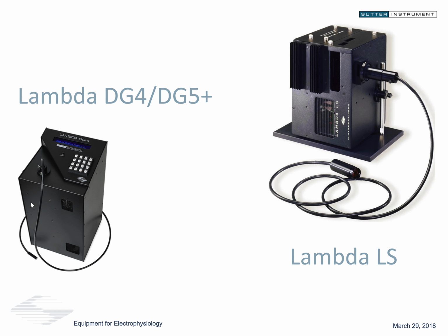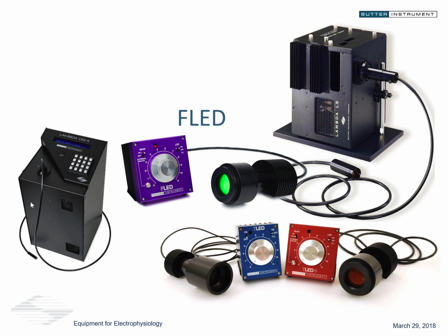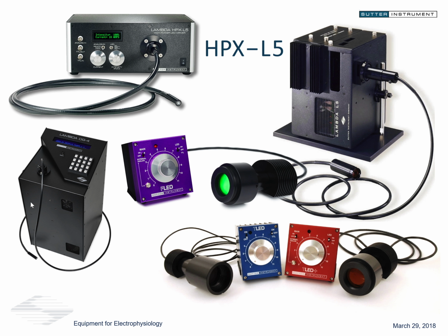Here's a question regarding the LEDs. In the age of LEDs, is there still a reason to use a conventional light source? Yes, but that argument is becoming harder and harder to make every day. I can think of some right off the bat where, for example, more than 4 channels of excitation might be needed, in which case you would be better served by a xenon light source and potentially a high-speed filter wheel, for example, that could open up to maybe 10 different excitation wavelengths as opposed to being limited by 4. So that's a potential application area where one might still turn towards the xenon lamps.